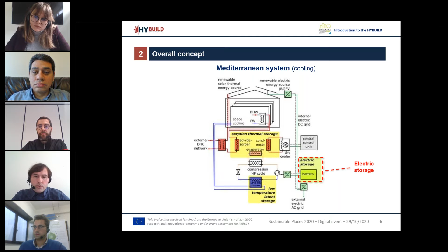Here also there is latent storage, but in this case it is based on phase change material located at the outlet, at the discharge of the compressor of a heat pump, to store the high temperature refrigerant and the sensible part of the energy coming out from the heat pump. The heat pump is fed directly from a DC bus, and the evaporator is located outside.